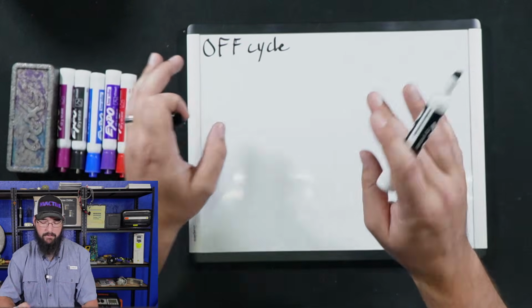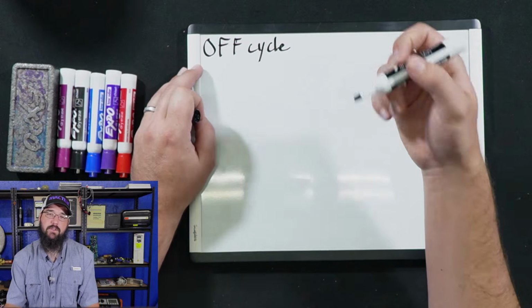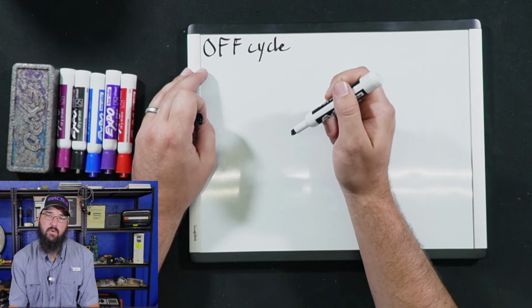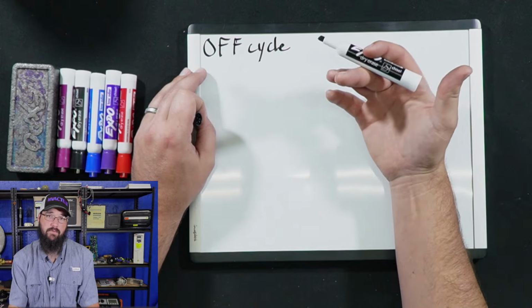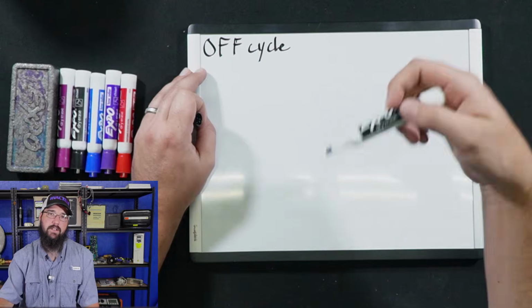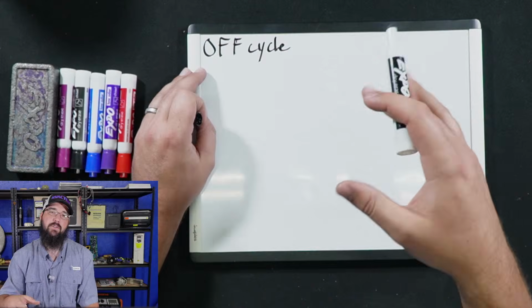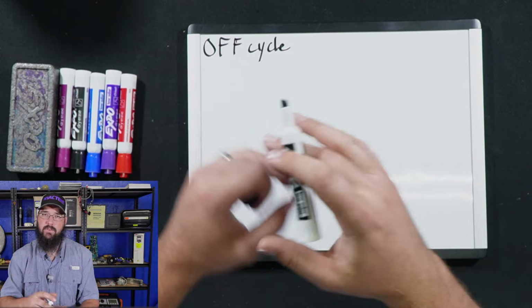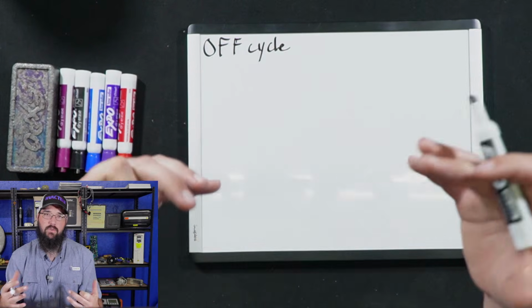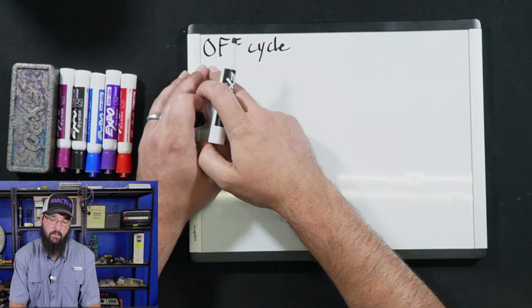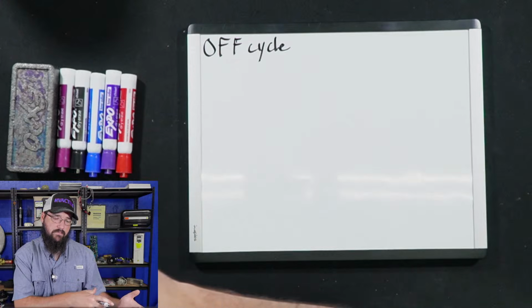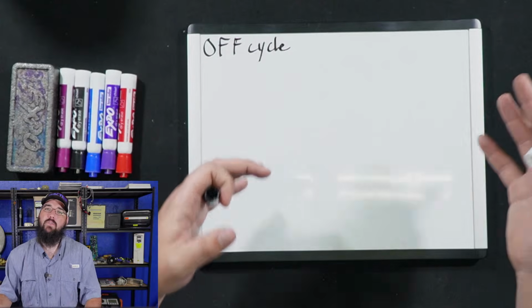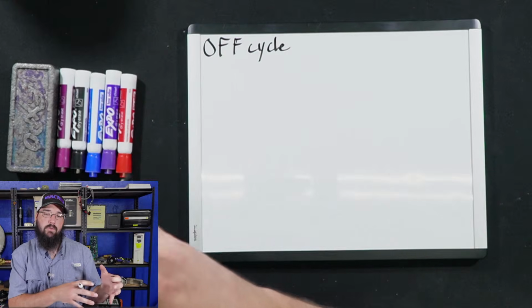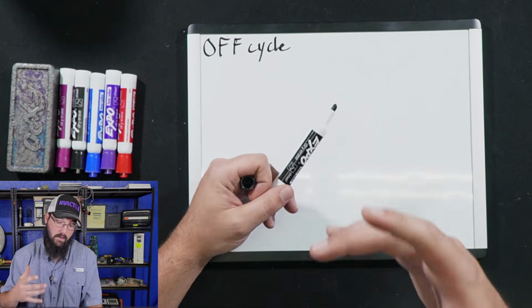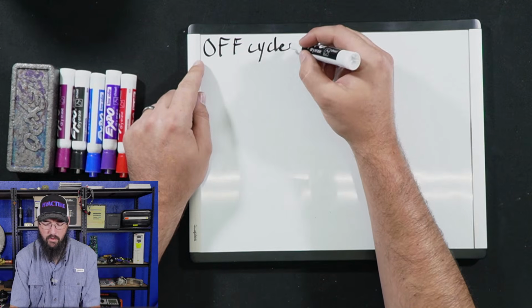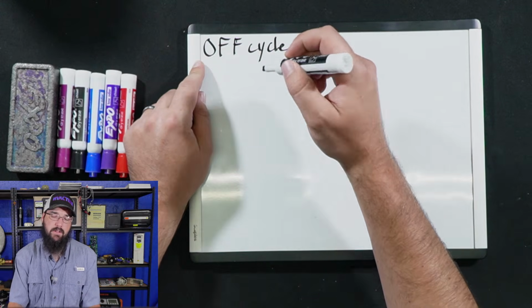So there's a balance. We have to calibrate a lot of the eductors in the field. If that eductor is not set properly on the valves, you can overfeed your oil return line coming through the eductor, and that's going to introduce a lot of refrigerant into our oil sump. So if that oil sump is heavily entrained in refrigerant, even though the heater is functioning and we're technically at temperature, when that machine goes to shut down, if that heater for some reason didn't work correctly, or we just had too much refrigerant entrained in the oil, we could end up causing what would be considered an off-cycle migration, where that refrigerant ends up carrying that oil to the coldest point in the system, which is likely, or should be, our evaporator. So all that oil is just going to get sucked straight to the evap and moved with that refrigerant as it goes. So an off-cycle migration due to an oil heater, something like that, would be one example.